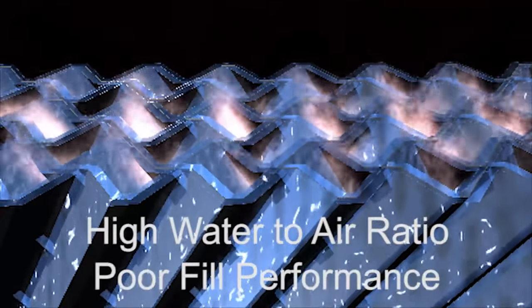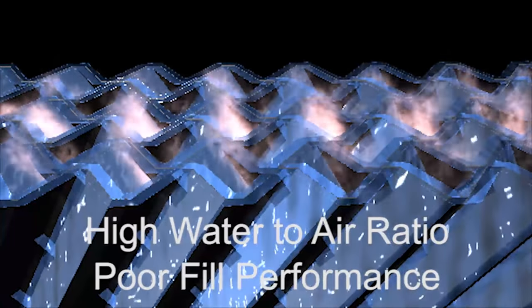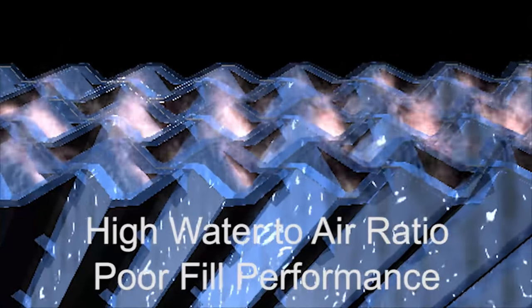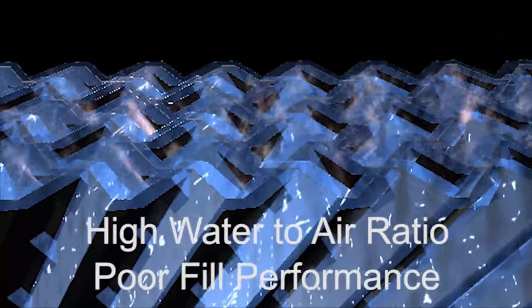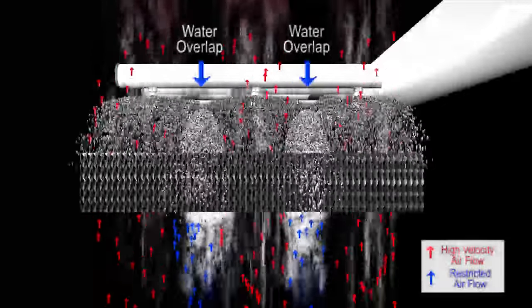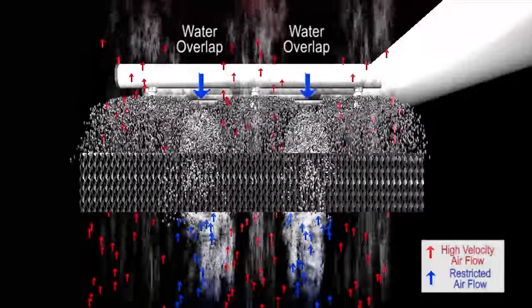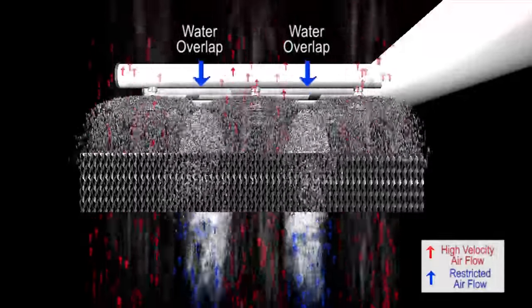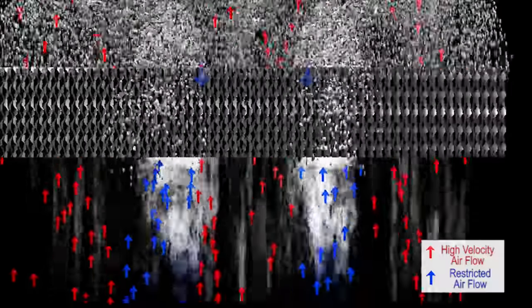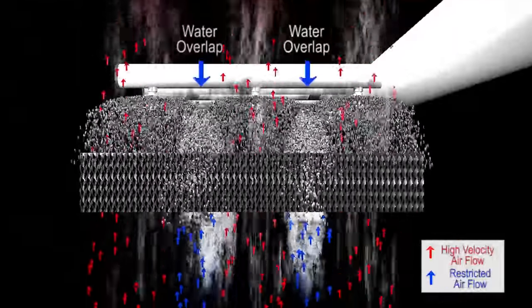Any deviation in this 1 to 3 ratio of air to water mixture will significantly degrade the performance of the cellular film media. So here is what happens when you overlap or flood the fill media. As you can see in the graphic, the water loading becomes heavy where the overlap occurs. This overlap creates a high-pressure drop, restricting airflow in these areas. The blue arrows depict the restriction to the airflow, resulting from the high-pressure drop and the heavy water loading of the overlap.